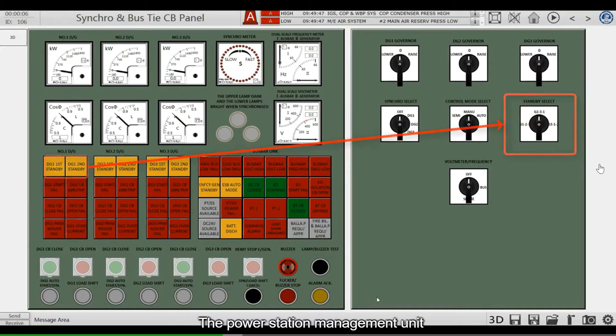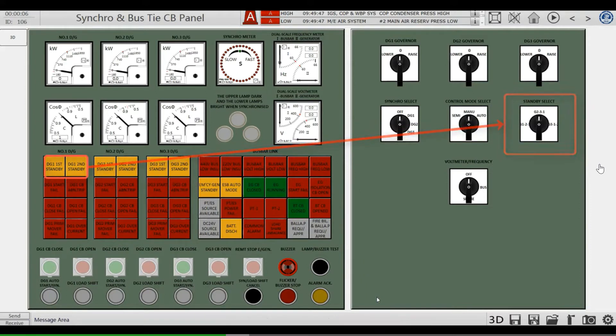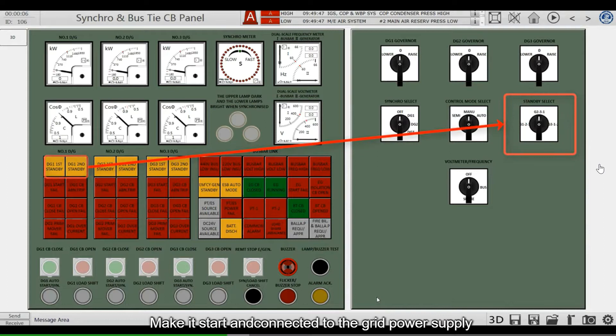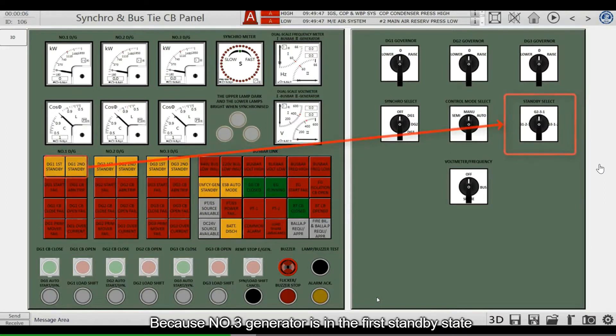the power station management unit will issue a start order to number 3 generator, making it start and connect to the grid power supply, because number 3 generator is in the first standby state.